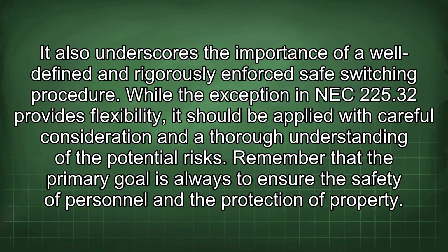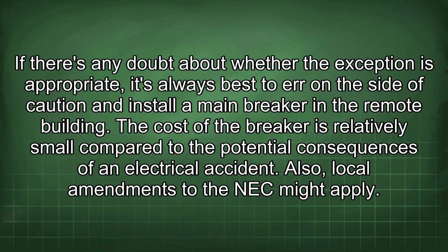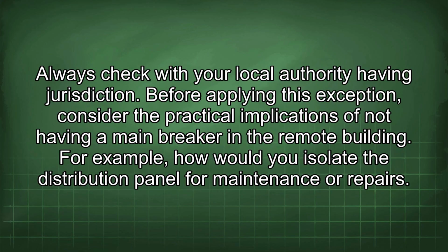Remember that the primary goal is always to ensure the safety of personnel and the protection of property. If there's any doubt about whether the exception is appropriate, it's always best to err on the side of caution and install a main breaker in the remote building. The cost of the breaker is relatively small compared to the potential consequences of an electrical accident. Also, local amendments to the NEC might apply. Always check with your local authority having jurisdiction.